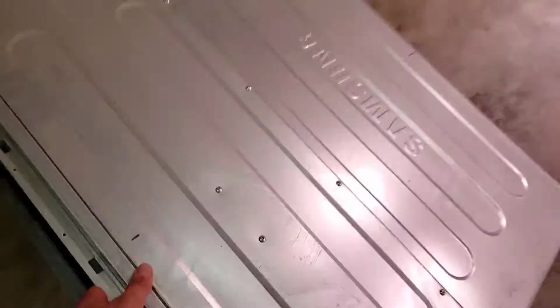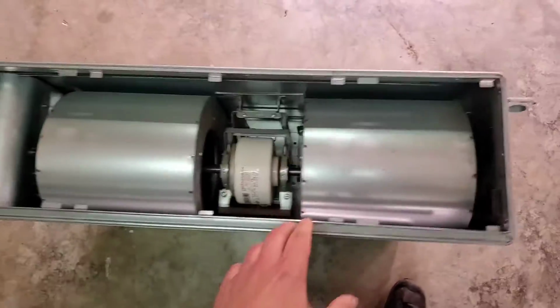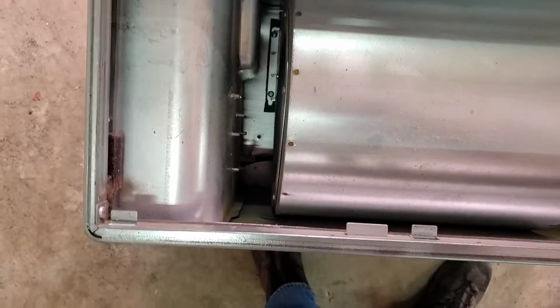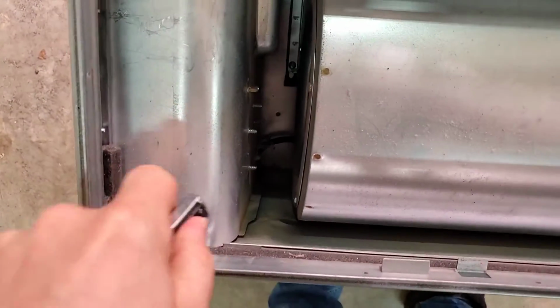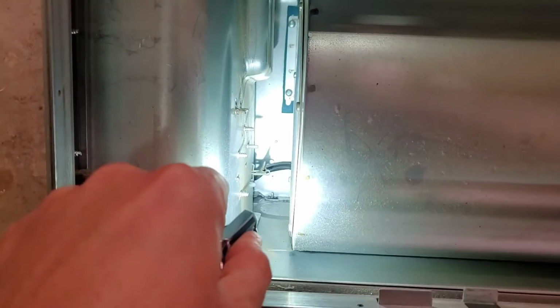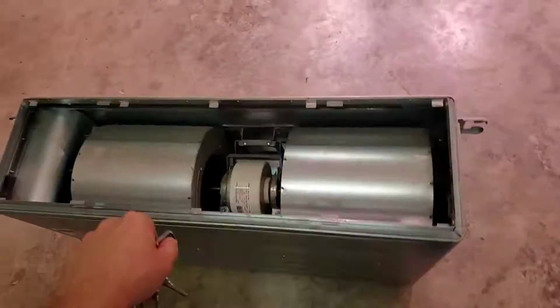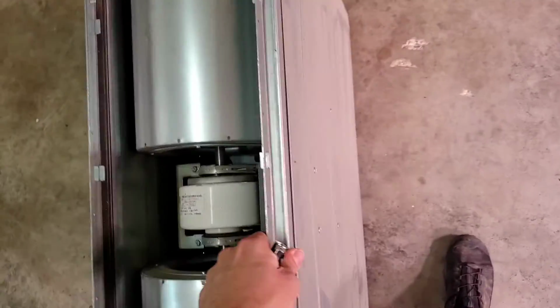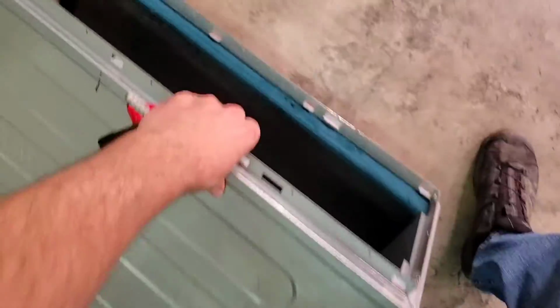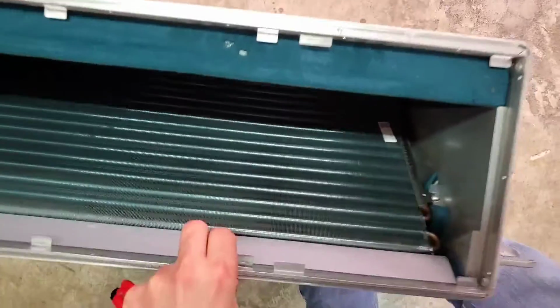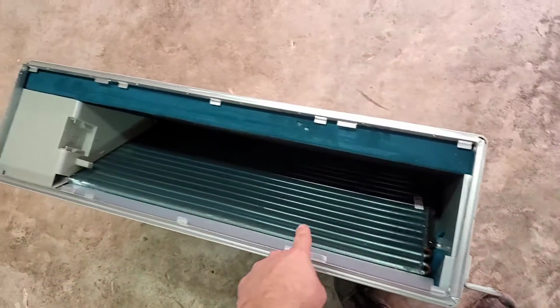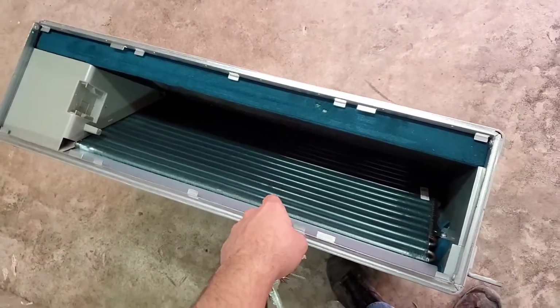Just in case you didn't know, this right here is a ducted air handler made by Samsung, and you can't really see it, but I've got a light here. There's the indoor sensor that measures the air passing across this air handler. And then those two sensors that we're going to measure the resistance on in a minute, the 10 kilo ohm sensors, are going to be located on the indoor heat exchanger for this Samsung ducted unit.